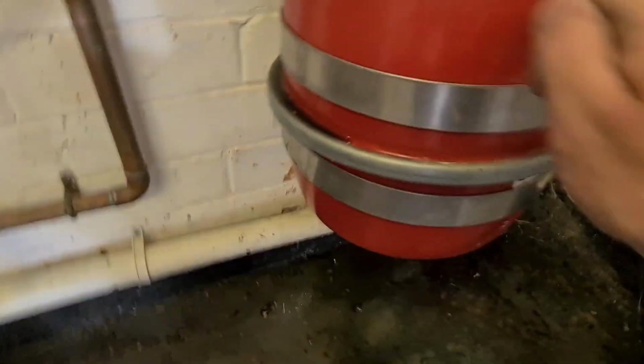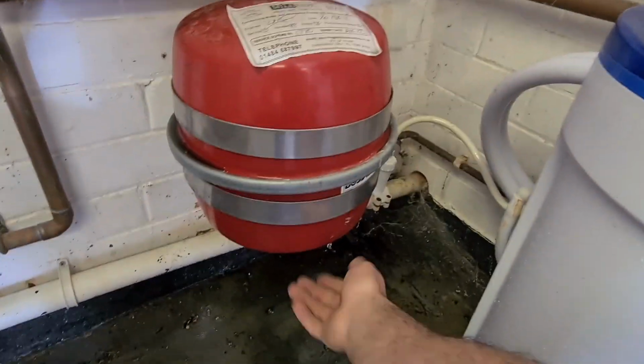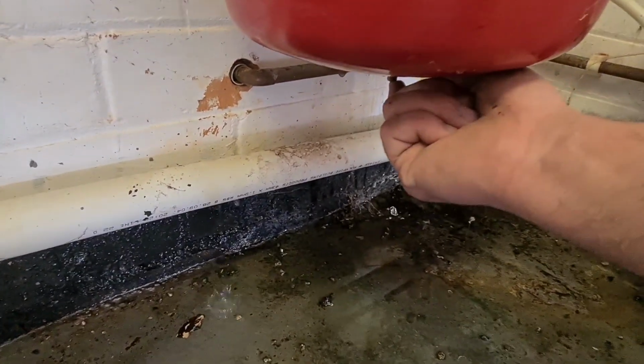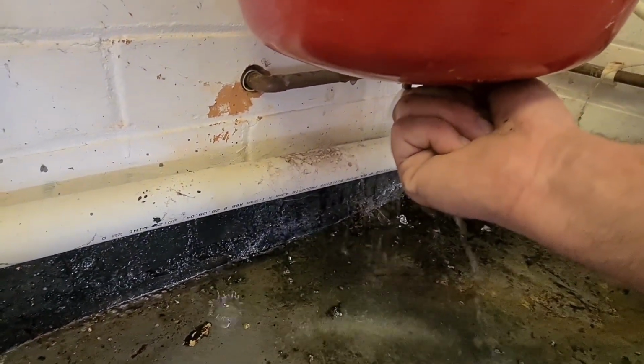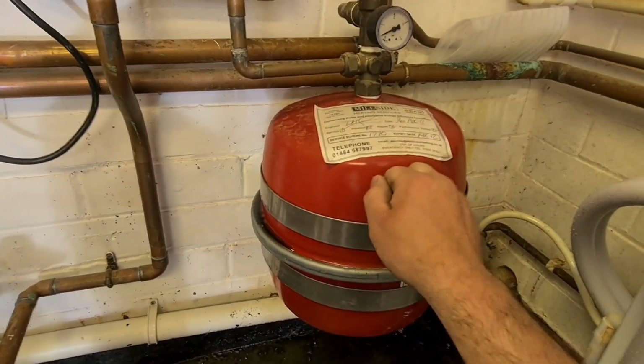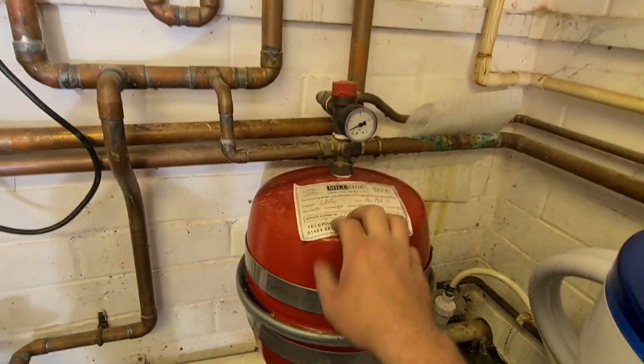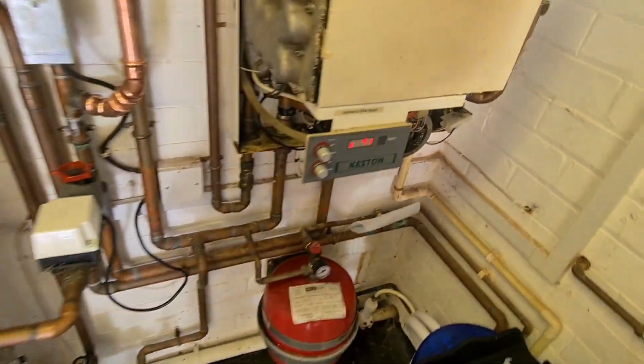This has totally failed though. When I whip the bottom of that off, it's leaking water from underneath, so you can see. So I'm going to get it up and running for now, just while I can, and then I'll have to go get one of these as well. Again, it's not an issue, I'd rather just see if I can get this going now, just to prove that the system is doing what it should be doing.